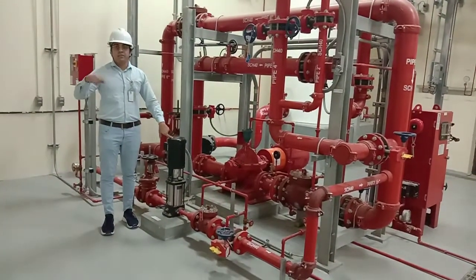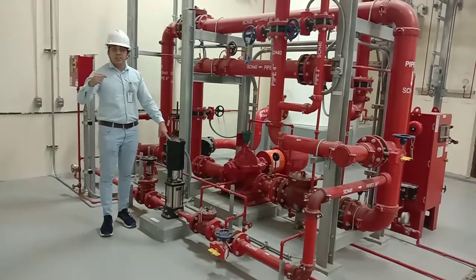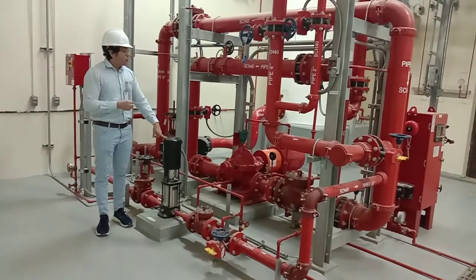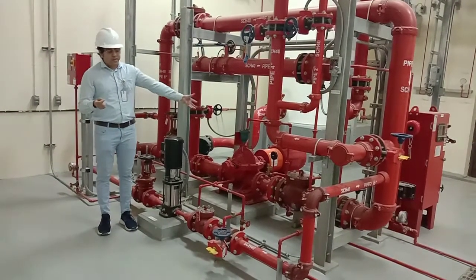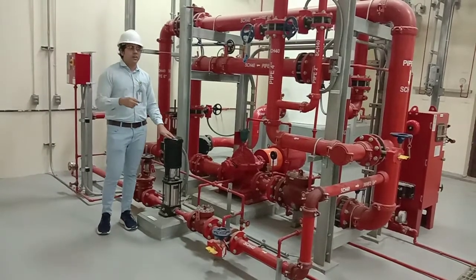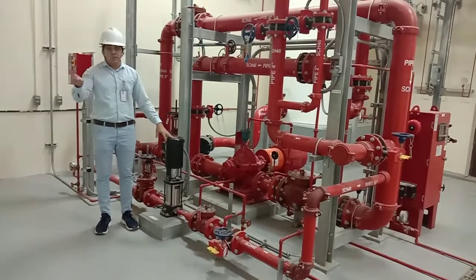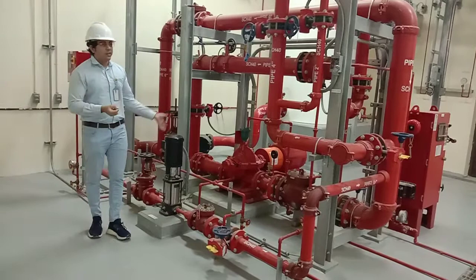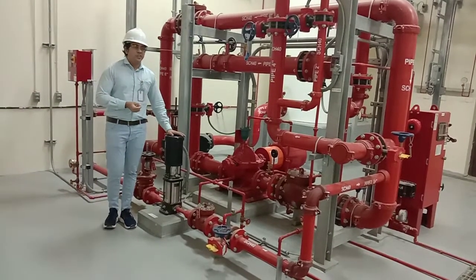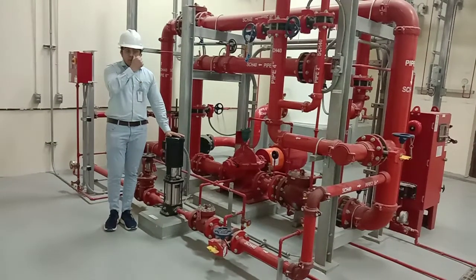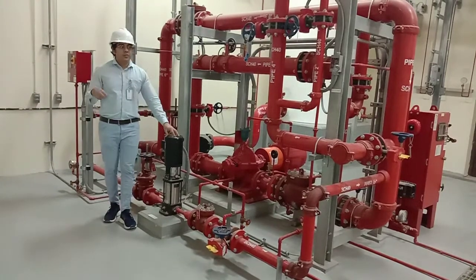Maybe let's say 10 times a day for 1 year, 2 years, 10 years, or 5 years, right? By doing that, the main pump will fail. The bearing will be damaged and will need lots of maintenance. The performance of the pump will reduce. For that, we need a jockey pump, which will only maintain the pressure in the fire protection system.